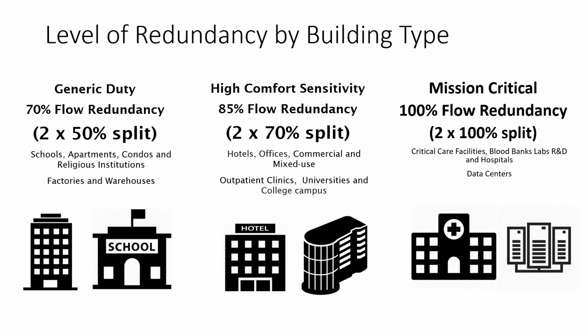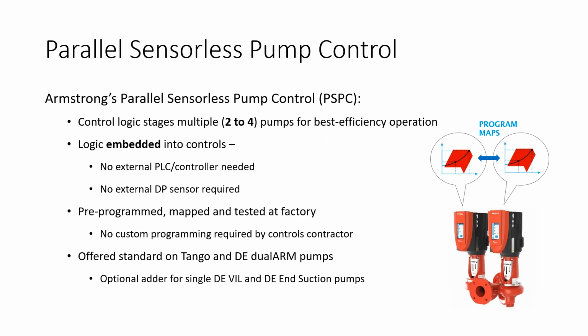And then of course your mission critical, which is your critical care facilities, hospitals, blood banks, R&D labs, and don't forget data centers where we keep all our computers. We'll keep those at 2 at 100% split, but we still have an option for you for savings as well with the dual arm selections. So the parallel sensorless control, pump control, Armstrong, we refer to as PSPC, it'll control from 2 to 4 pumps for best efficiency operation. It's different than what we generally design into a VFD. The logic embedded into the control, there's no PLC once again, no differential pressure because we're using design envelope, and it's pre-programmed and mapped and tested at the factory once again.